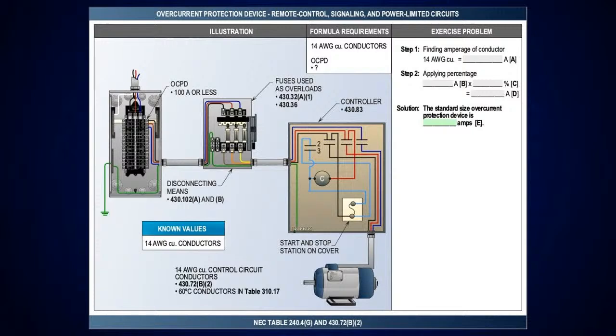And then here's an illustration where I have the controller and you've got the control conductors inside that enclosure. Just remember, we're doing a number 14 conductor. Because you're inside the controller, that's free air space. We're going to use table 310.17, then I'm going to use the 60°C column and take it at 400%.